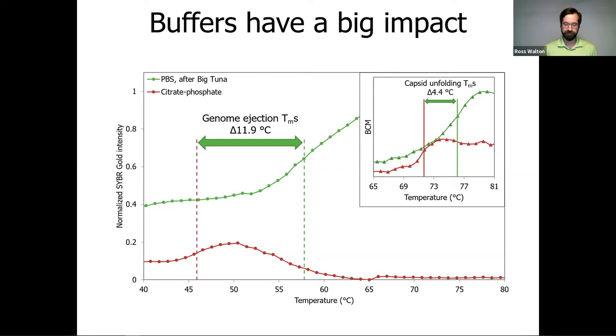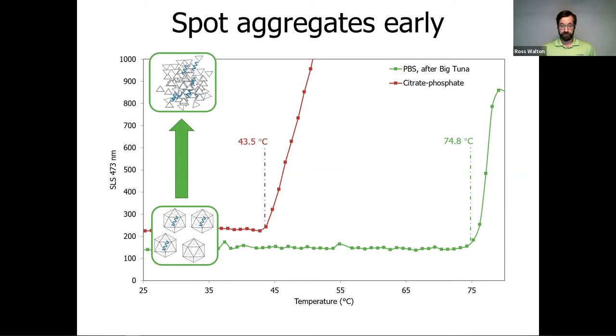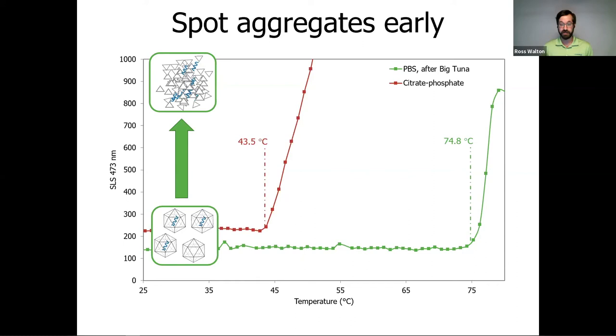UNCLE also lets you look at aggregates during a thermal ramp. Simultaneously with genome ejection, we were able to look at aggregate formation as temperature increased, because the static light scattering of our 473 nm laser also increased. We can assign a T-agg right where the SLS intensity starts to rise. The citrate phosphate buffer was already aggregating at room temperature, and that aggregation got significantly worse during thermal ramping, starting at about 43.5 degrees Celsius. Whereas in PBS, the AAV9 didn't start aggregating until about 75 degrees Celsius — much more thoroughly stable.